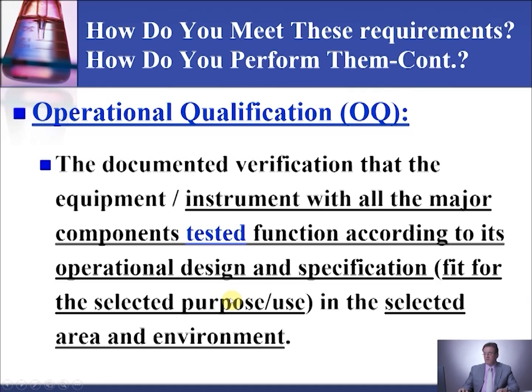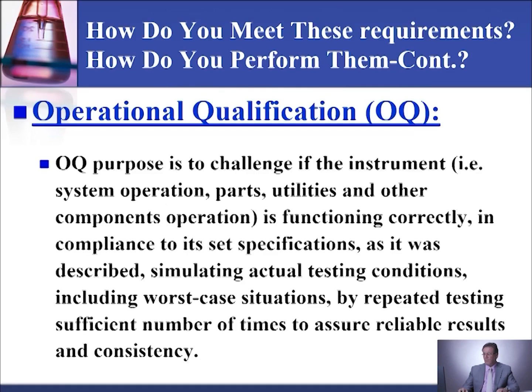Operational qualification is the documented verification that the equipment or instrument, with all the major components tested, functions according to its operational design and specification. In other words, fit for the selected purpose used in the selected area and environment. The purpose of operational qualification is to challenge whether the instrument, system operation, parts, utilities, and other components are functioning correctly in compliance with their set specifications as described, simulating actual testing conditions, including worst-case situations, by repeated testing a sufficient number of times to assure reliable results and consistency.